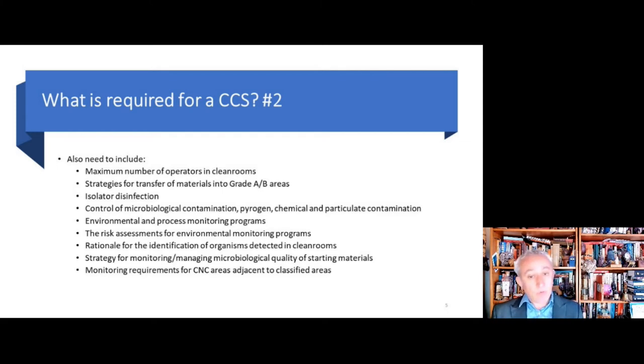If there is freeze drying, then control of the lyophilization process. To develop meaningful environmental monitoring including sample quantities, methods, and frequency. To ensure the environmental monitoring program is risk-based. To help guide the identification of organisms detected in different areas. Although we may do grade A and B isolate everything to species level as the annex indicates, a risk-based strategy can help develop the C and D microbiota profiling strategy. We can also use the strategy to help inform about monitoring and managing the microbial quality of starting materials and the overall way that we get goods and materials through different areas of different clean rooms through the contamination control cascade.